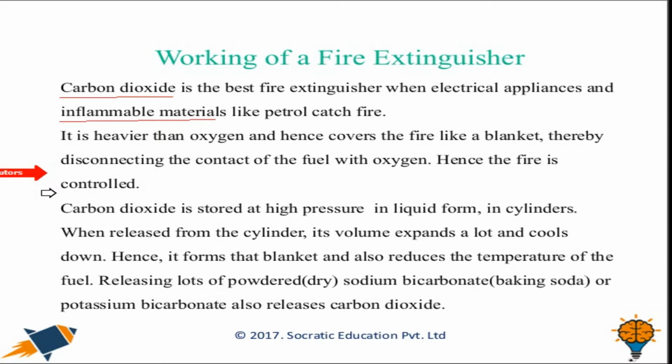It is heavier than oxygen and hence covers the fire like a blanket, thereby cutting off the contact of the fuel with oxygen, and the fire is controlled. So basically we remove the oxygen from the place, and the lack of oxygen controls the fire. Carbon dioxide is stored at high pressure in liquid form. So at high pressure it comes in liquid form.